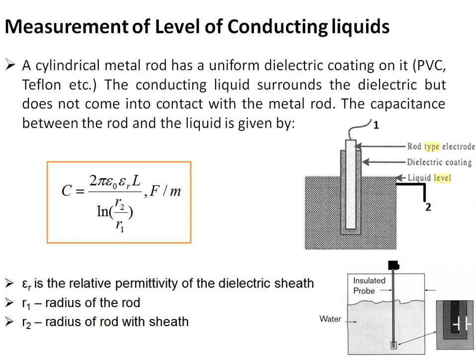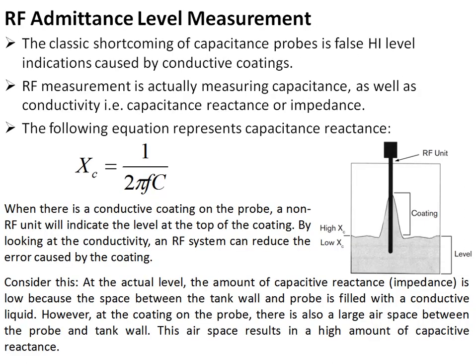The capacitance is given by C = 2π·ε₀·εᵣ·L / ln(r₂/r₁), where r₁ is the radius of the rod and r₂ is the radius of the rod including its sheath. The problem with capacitance type level measurement for conducting liquids is that the conducting liquid can coat the insulation, giving an erroneous signal.